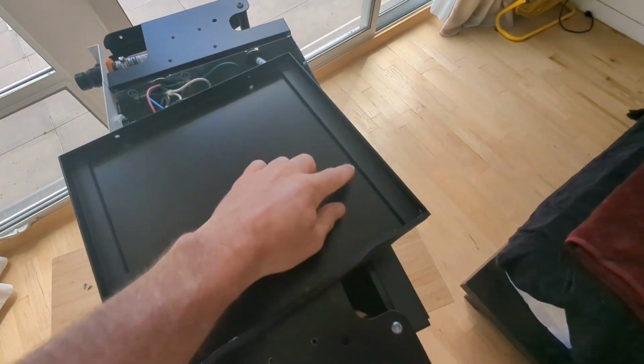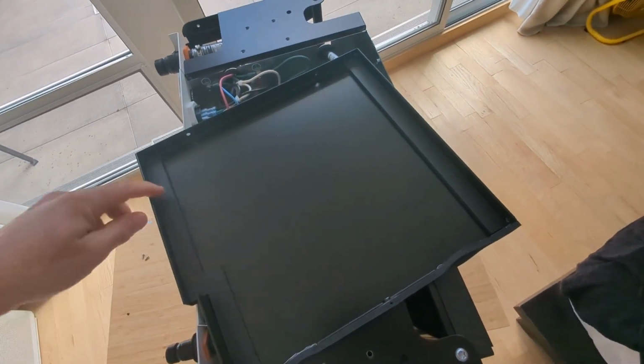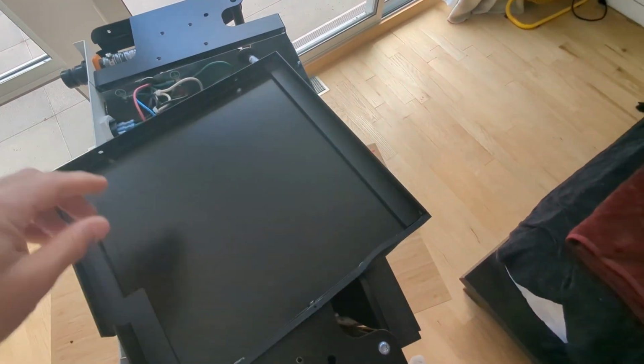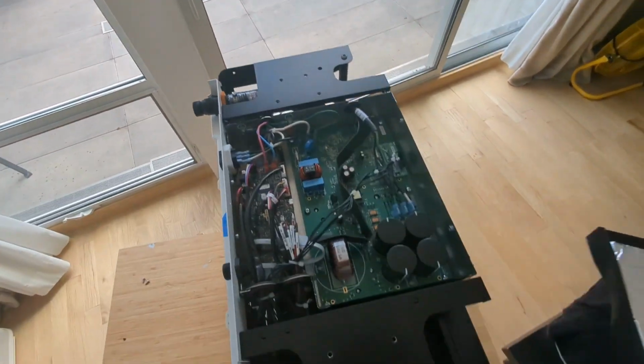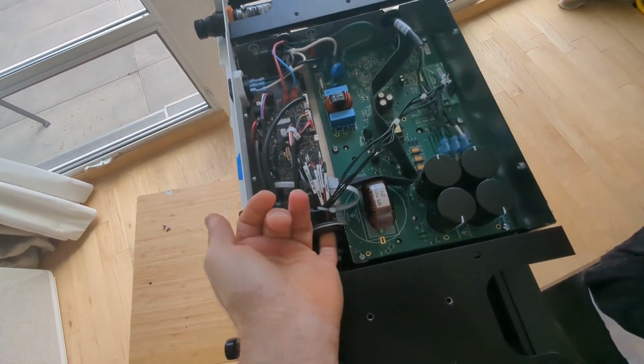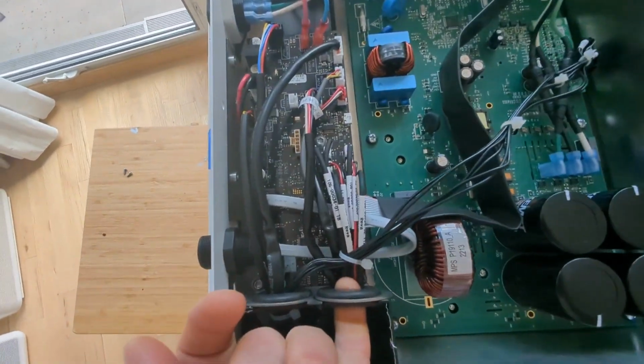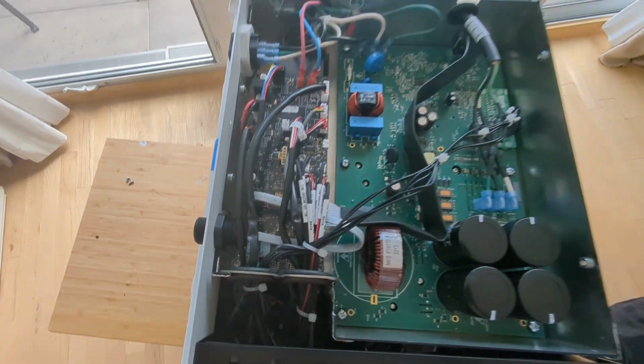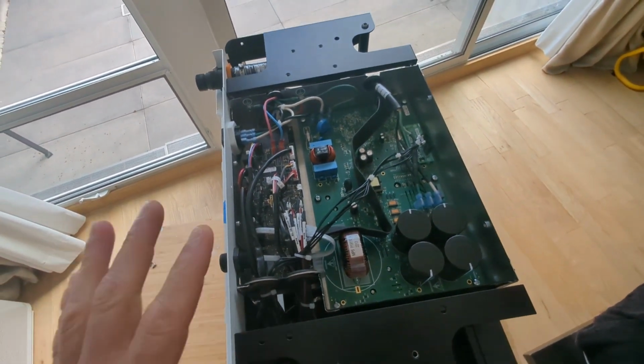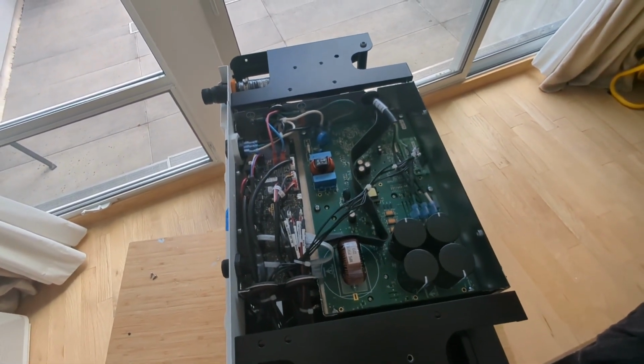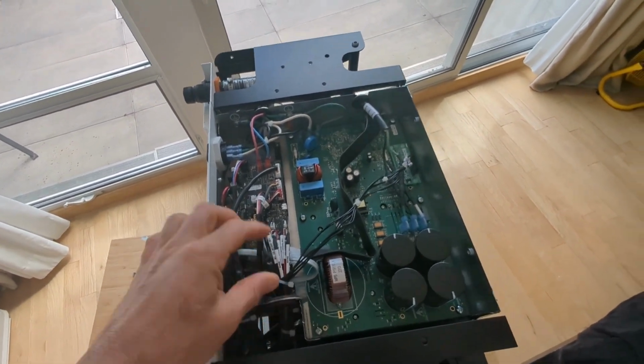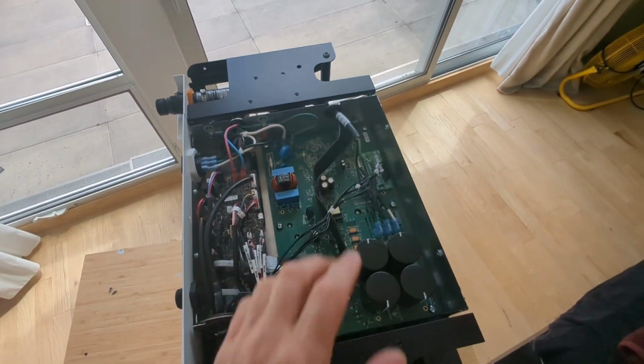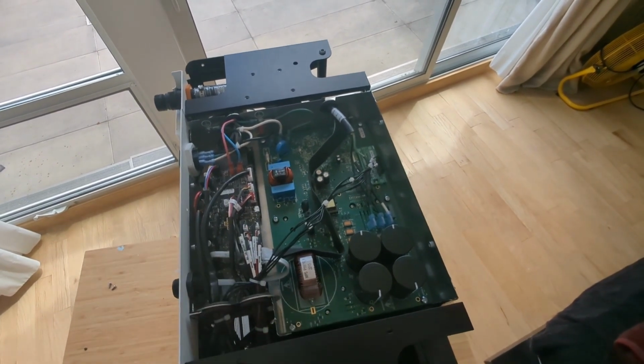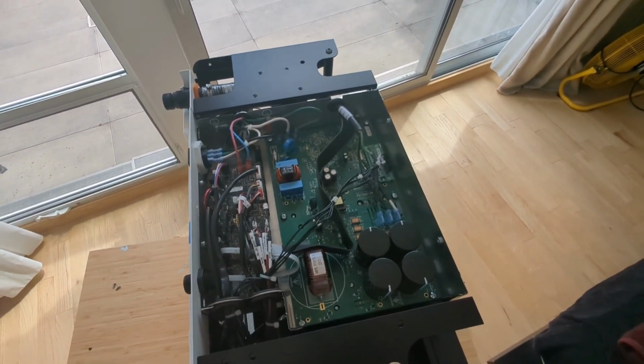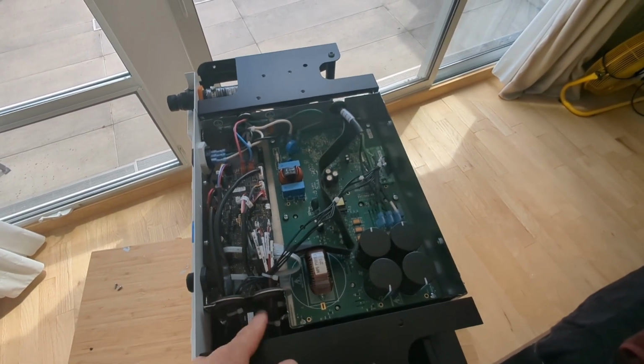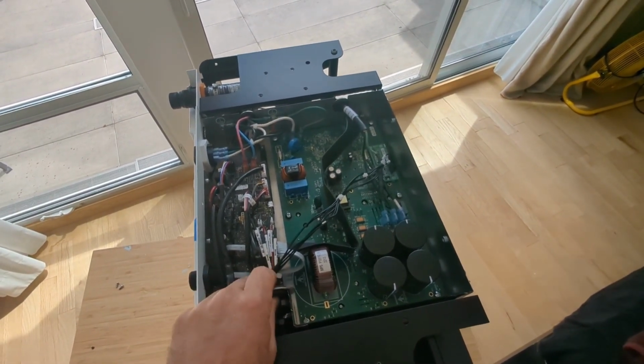Now, my first area of concern is that this is really not IP sealed. There's some foam gaskets here, but there are plenty of ways for stuff to get into that box. Most concerning is right here, where the wires go in through this hole. You can see it's just wide open, and I'm going to make a prediction right now that within the next couple of years, they're going to have some failures due to insects crawling in through this hole and making their home inside this controller box, which eventually is going to short something out or cause some corrosion on some lines. Those insects, boy, any hole you give them, they will use.